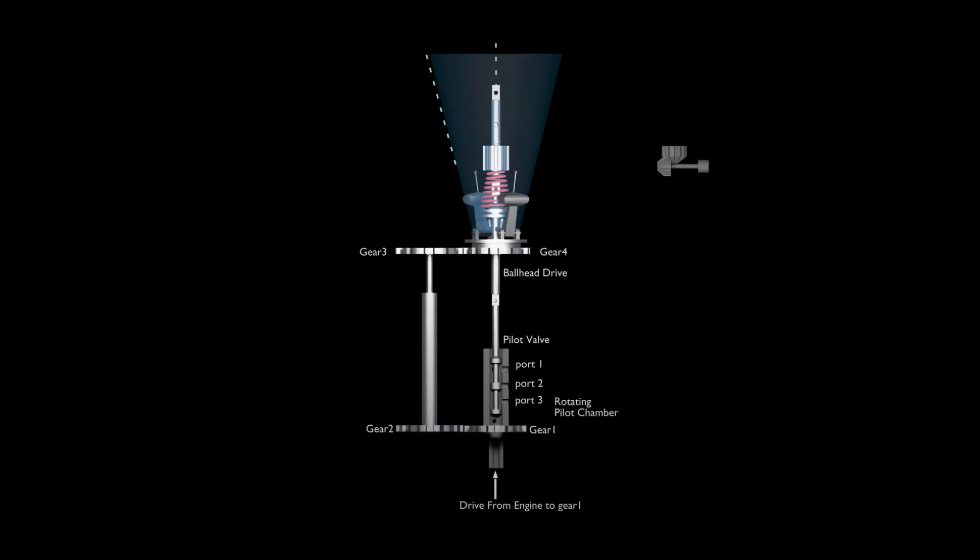But will this setup work? The answer is no, it will not. To answer the question as to why this will not work, we need to address another aspect here. There is always a lag or delay in engine RPM response, inherent with all engine governor systems, with respect to the rack setting or power piston setting at an instant while there is a change or movement of the racks, either increasing or decreasing fuel.